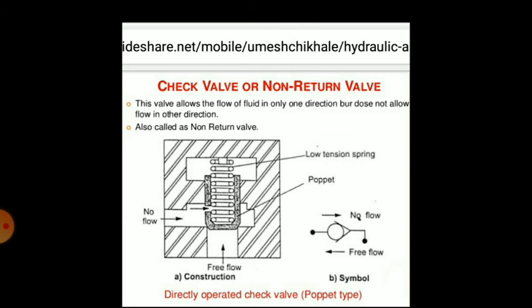You can see the construction of the check valve or non-return valve — it is a poppet-type valve, also called a directly operated check valve. You can also see the symbol of a check valve: in one direction the arrow indicates no flow, and in the opposite direction there is free flow. The purpose of the check valve is to block the flow of fluid in a given direction but to permit unrestricted flow in the opposite direction.